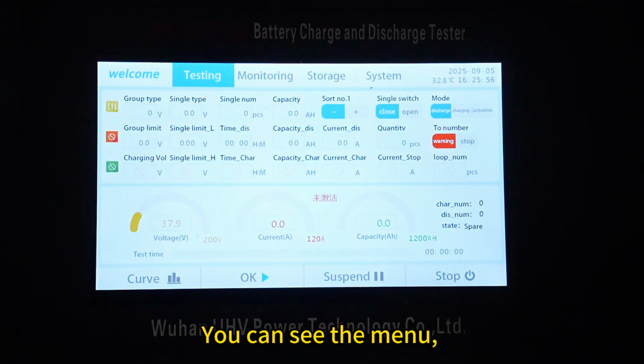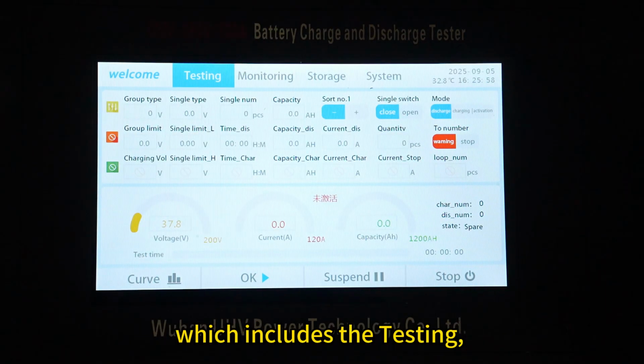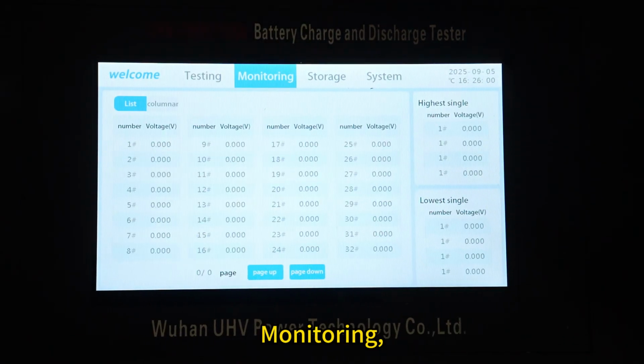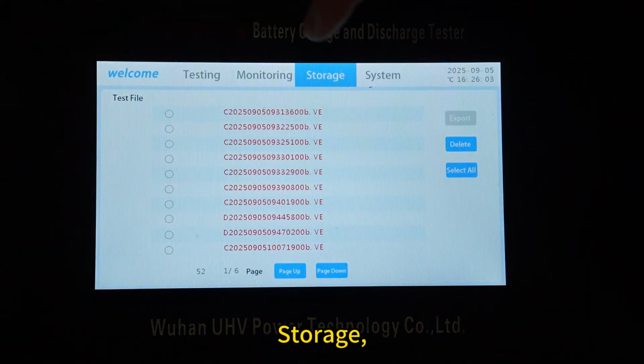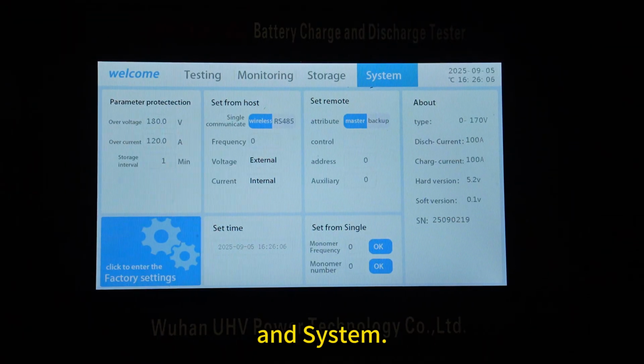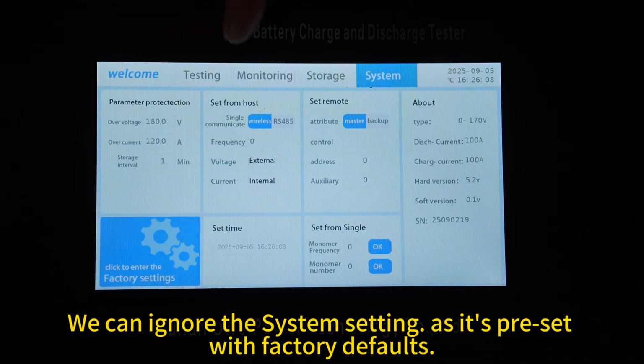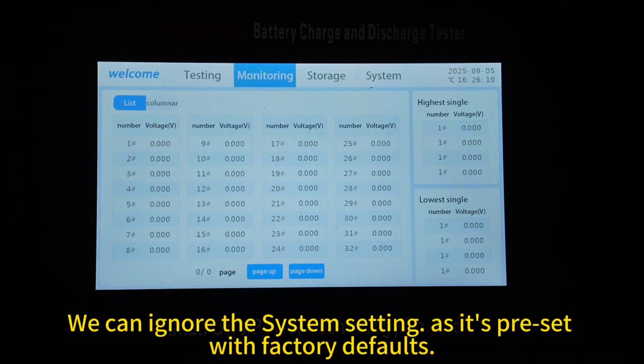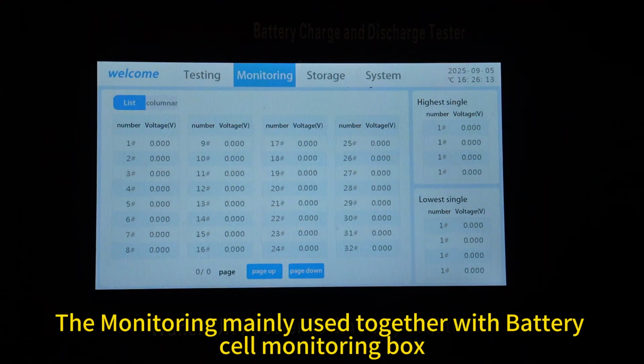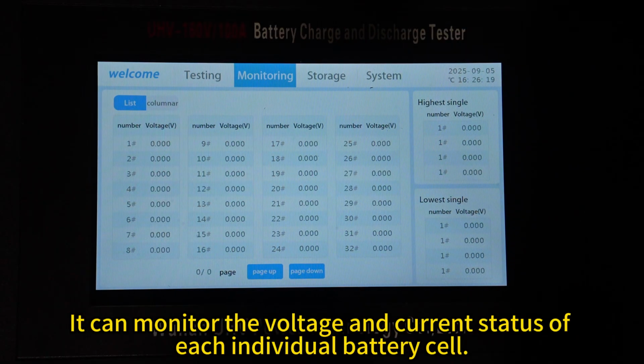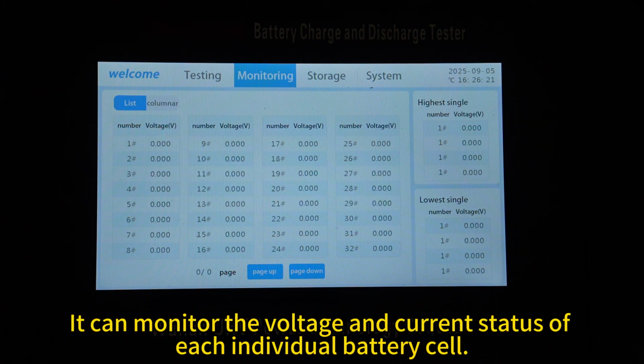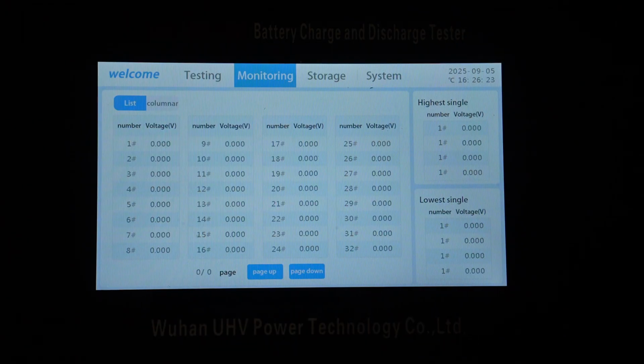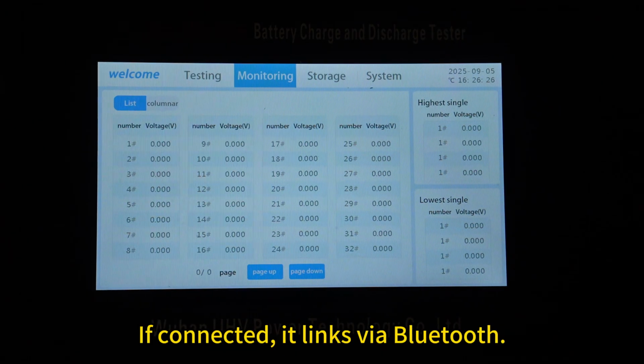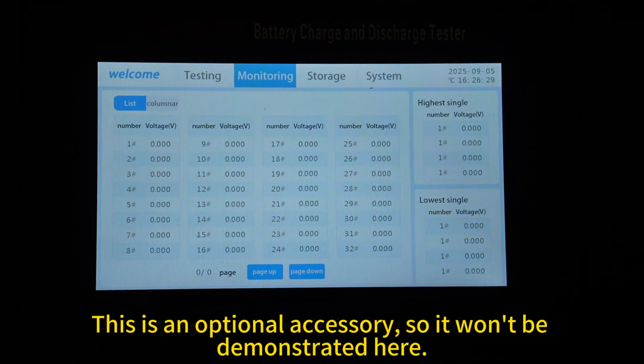You can see the menu, which includes the testing, monitoring, storage, and system. We can ignore the system setting, as it's preset with factory defaults. The monitoring is mainly used together with the battery cell monitoring box. It can monitor the voltage and current status of each individual battery cell. If connected, it links via Bluetooth. This is an optional accessory, so it won't be demonstrated here.